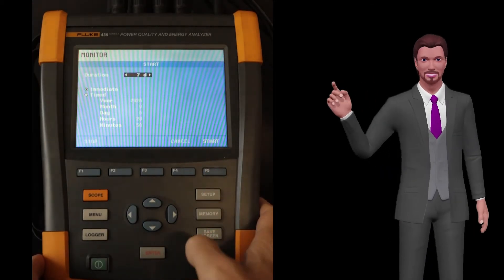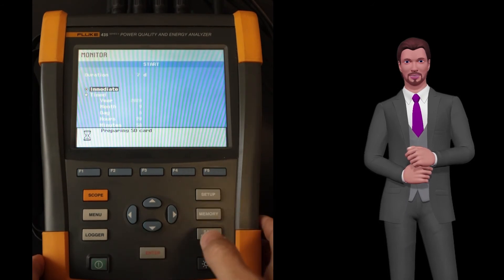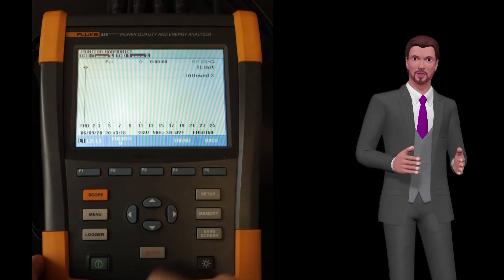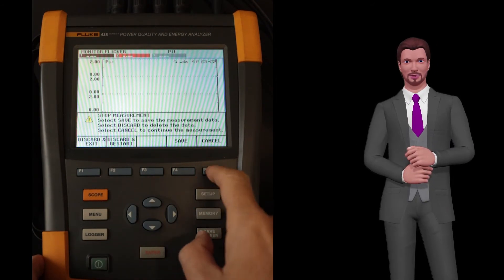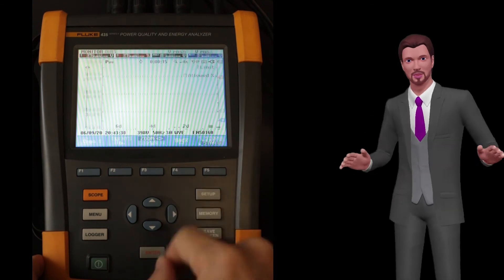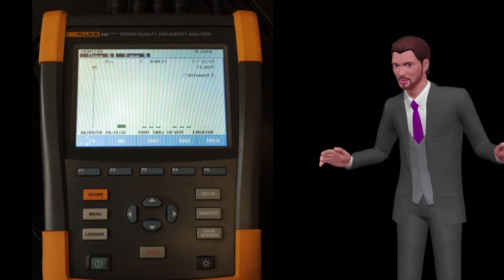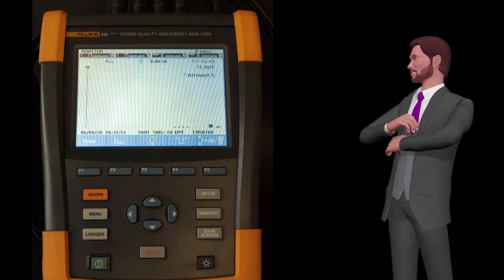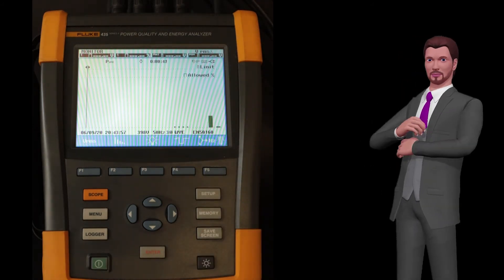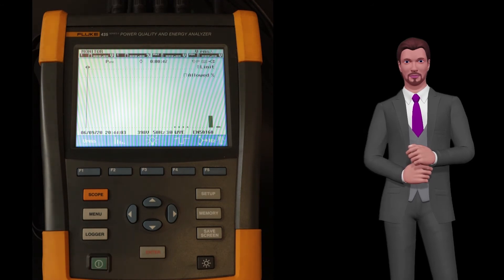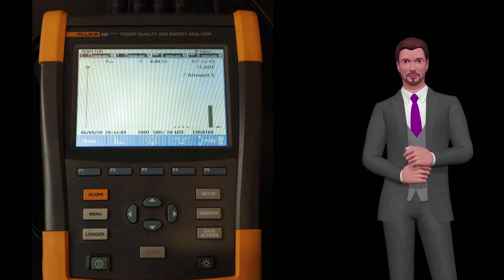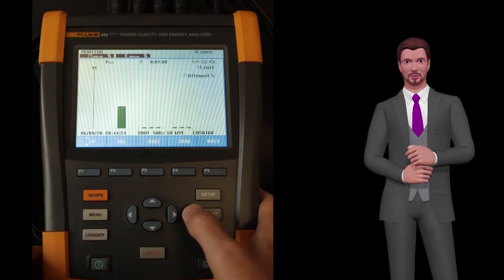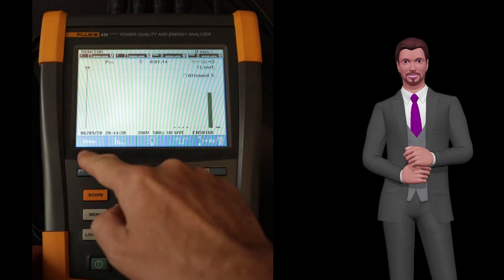The last function in this group is the monitor function. This function is very important for those who want to make an analysis of electrical quality according to regulations, for example according to the EN 50160 standard. In real time the instrument measures parameters associated with the quality of the voltage, such as voltage limits, fluctuations, harmonics, voltage imbalance, flicker, etc., and compares them with the standard. We have all the data in numerical form and trends, but the unit also provides a color bar graph to show, at a glance, compliance with the standard.